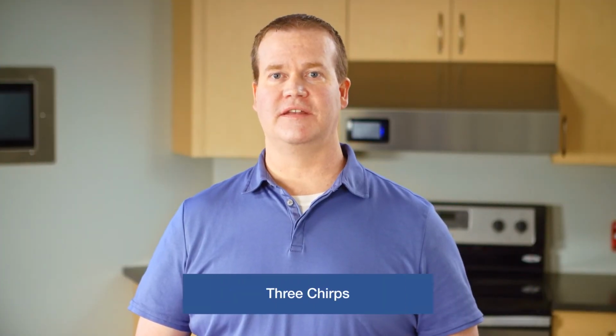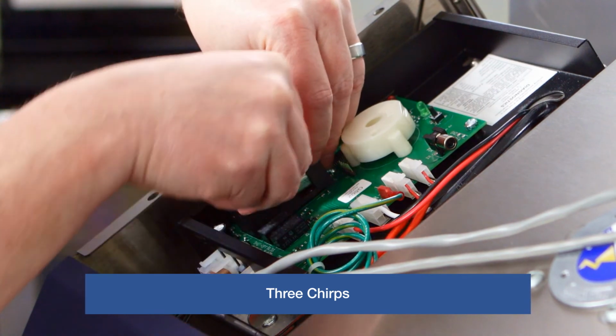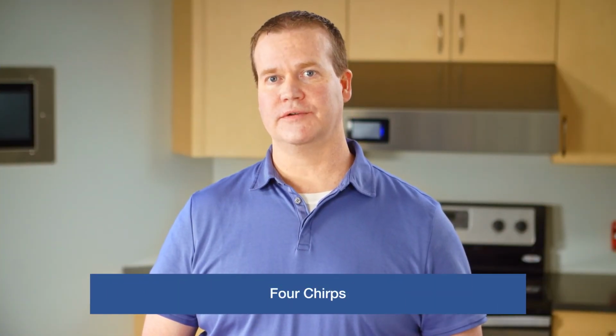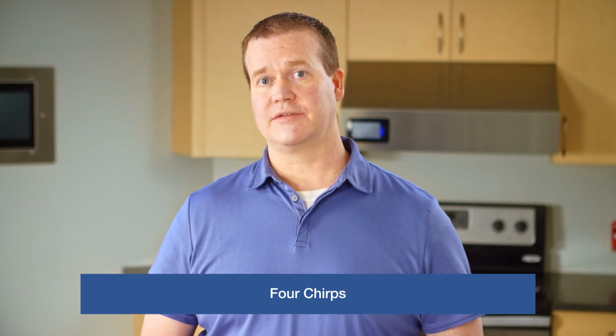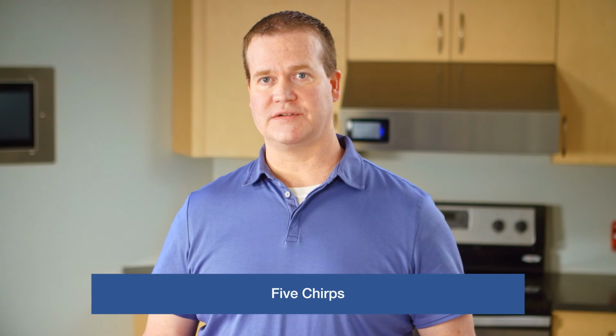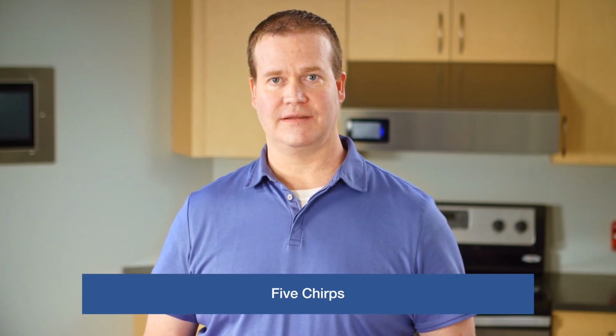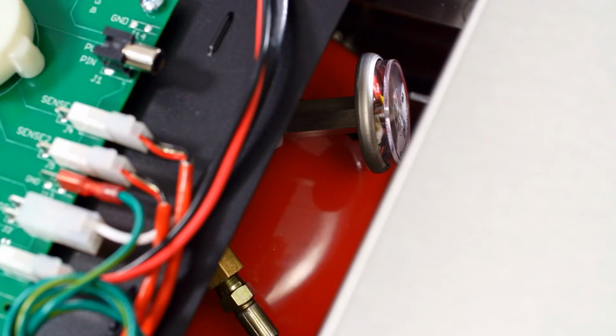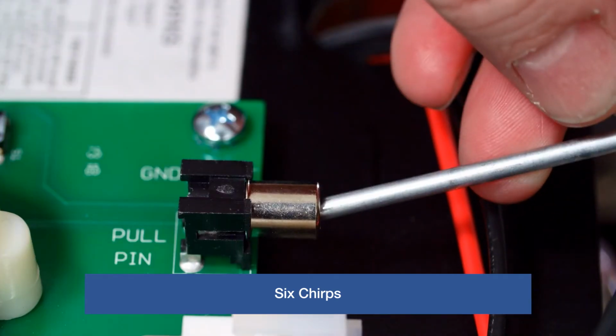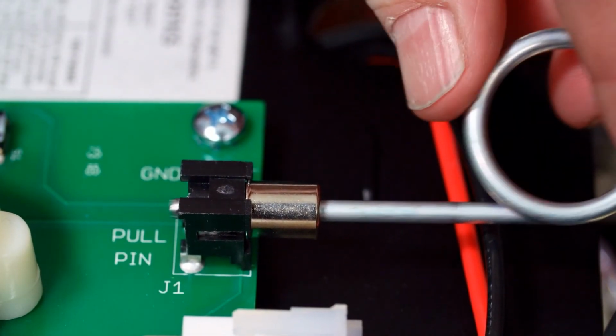3 chirps indicate the 9-volt battery voltage is low. Simply replace the battery. 4 chirps indicate the suppression tank solenoid circuit has a problem. Check the wiring for loose connections or faulty wiring. If connections and wiring test OK, replace the solenoid. 5 chirps indicate low pressure is detected in the fire suppression tank. Check the suppression tank gauge. Recharge or replace the tank as required. 6 chirps indicate the pull pin is not installed in the control board socket. Verify that the pin is properly installed.